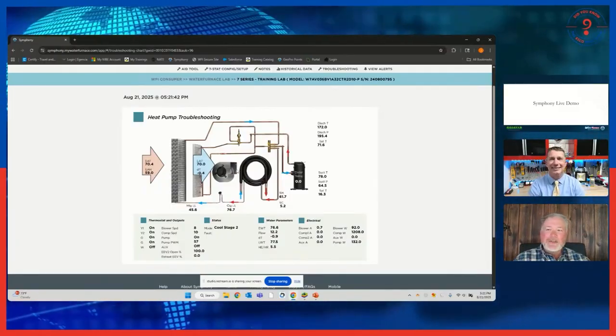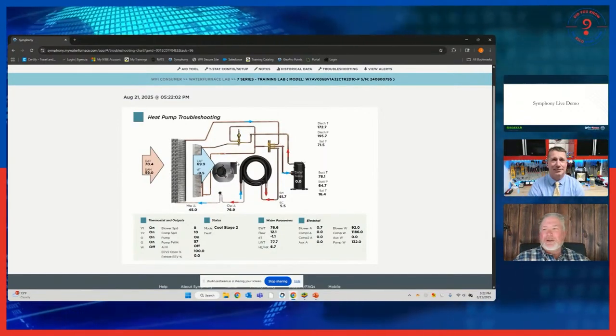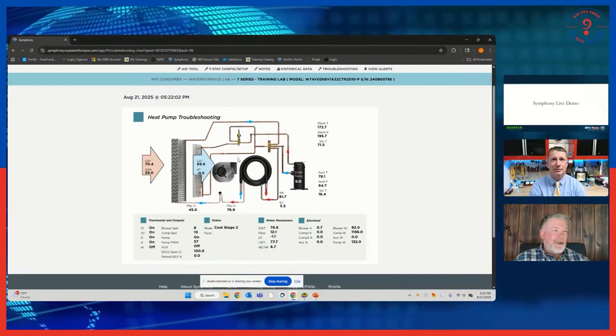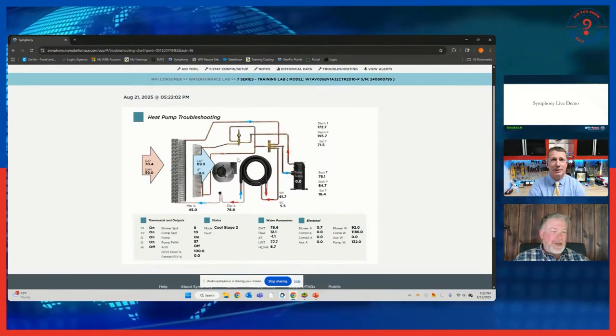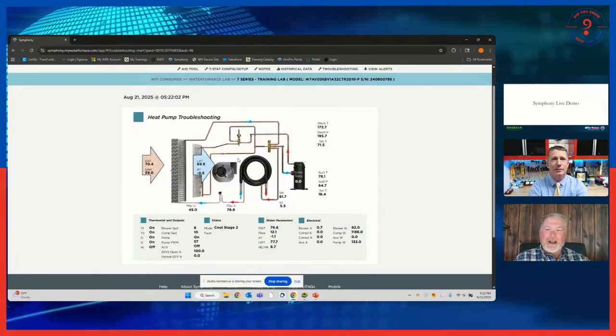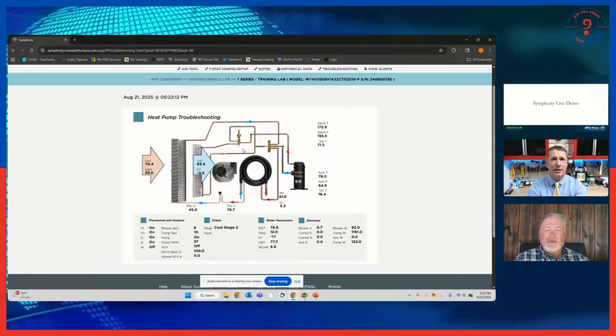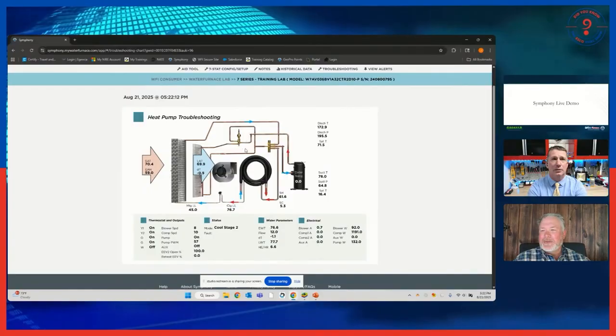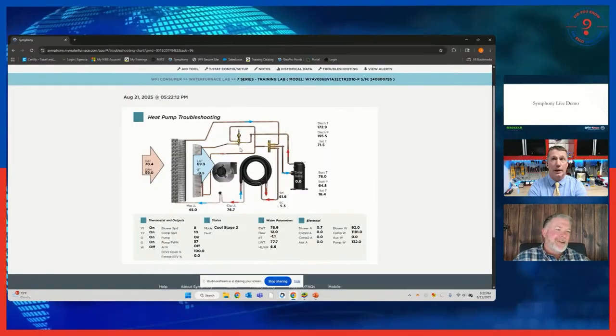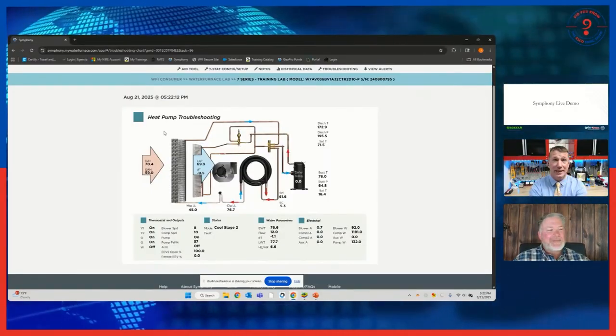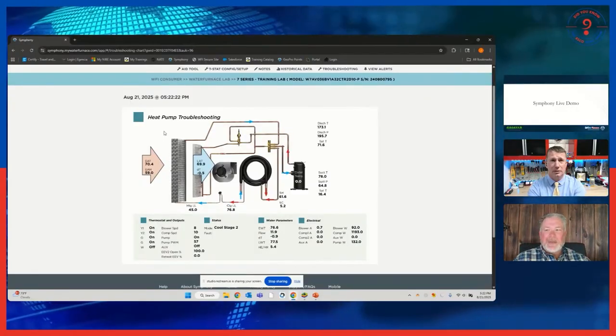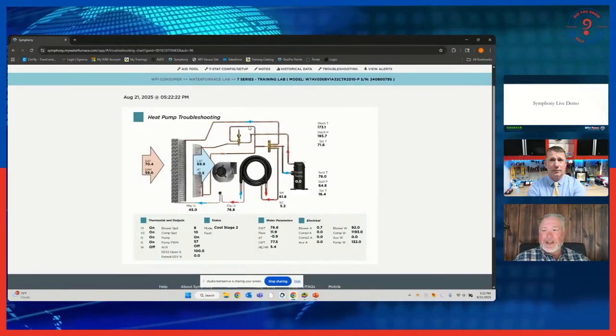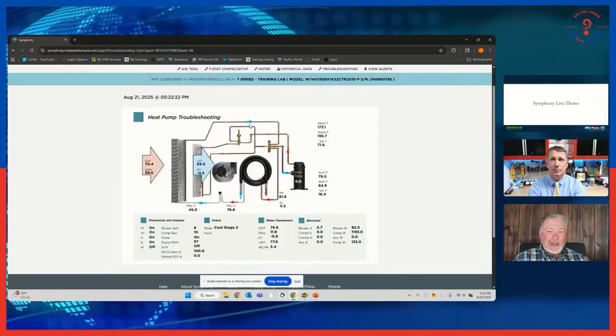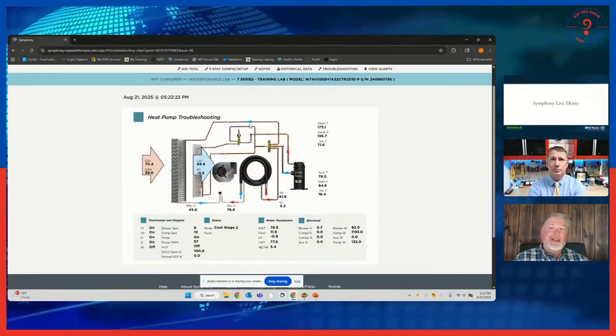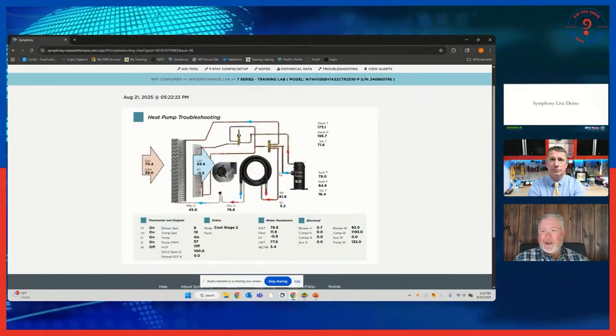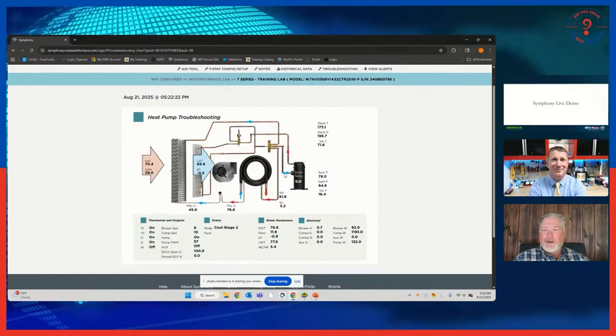Now this unit's a little different — a little more complicated. This is what we call our OptiDry unit, a hot gas reheat unit with bypass modulating hot gas, so that reheat valve and secondary coil are in there. Maybe not the best choice to show everybody today, but it's pretty neat because it shows we have that capability too, and we can see what the entire system's doing. If you don't do geothermal every day and forget which way the refrigerant's going, we've got arrows showing you where everything goes.